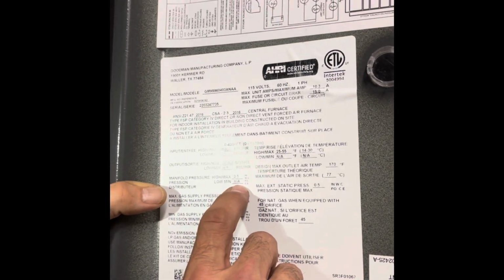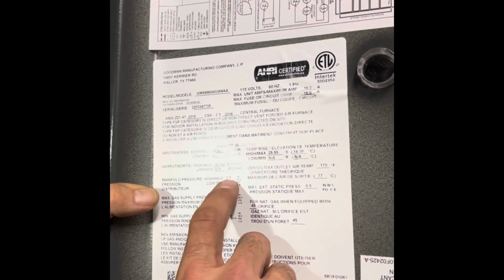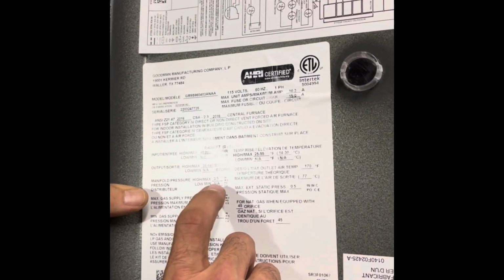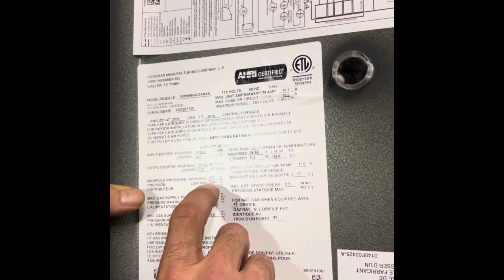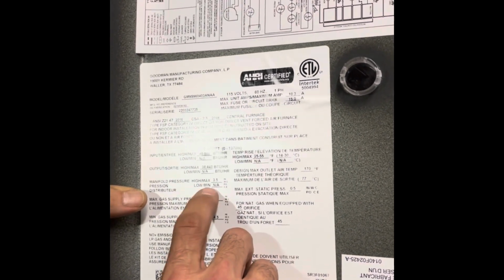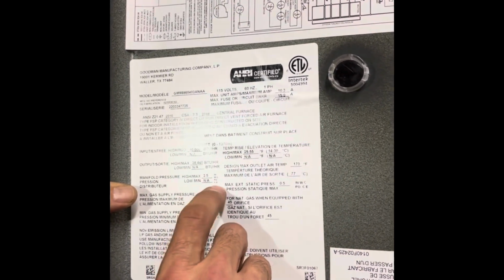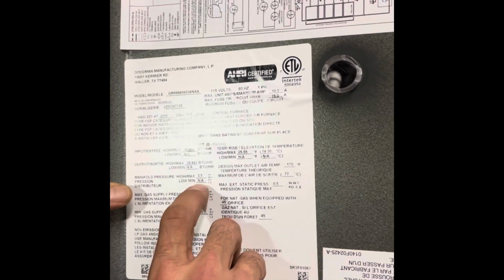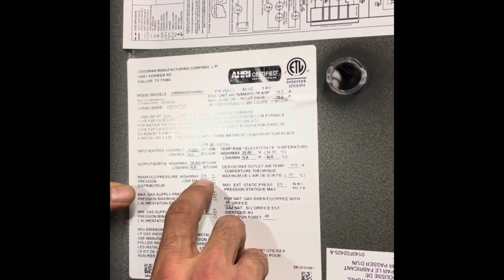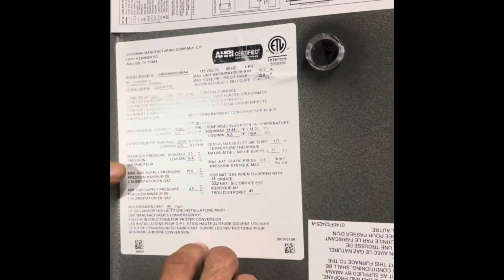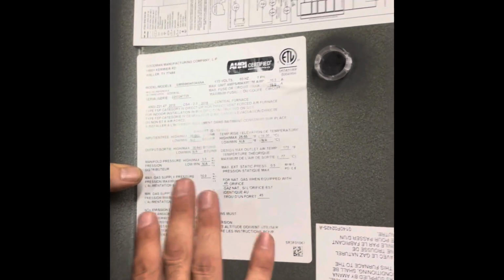Low pressure is not applicable. So again, this is a high heat only furnace. If we had a two-stage furnace, meaning it had low heat mode and high heat mode, there would be a value in this part here. So with this furnace, when I start it up, I want to make sure my number is not over 3.5. Other than that, that's about all I need to know.